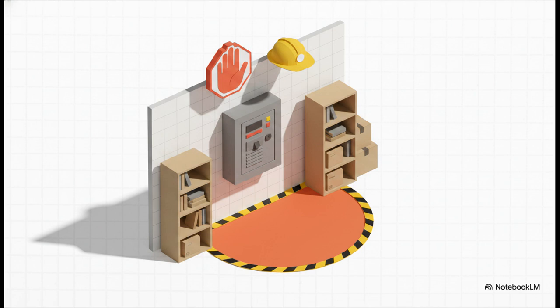Number 3, never block your panel. The National Electrical Code strictly requires a minimum 36-inch clearance zone in front of it. You can't put bookshelves, storage boxes, or furniture in front of it. In an emergency, you need instant access. And finally, never defeat a tripping breaker by replacing it with a higher rated one. If a 15-amp breaker keeps tripping, jamming a 20-amp breaker in there doesn't fix the problem. It literally just allows the wiring in your walls to overheat and potentially catch fire.